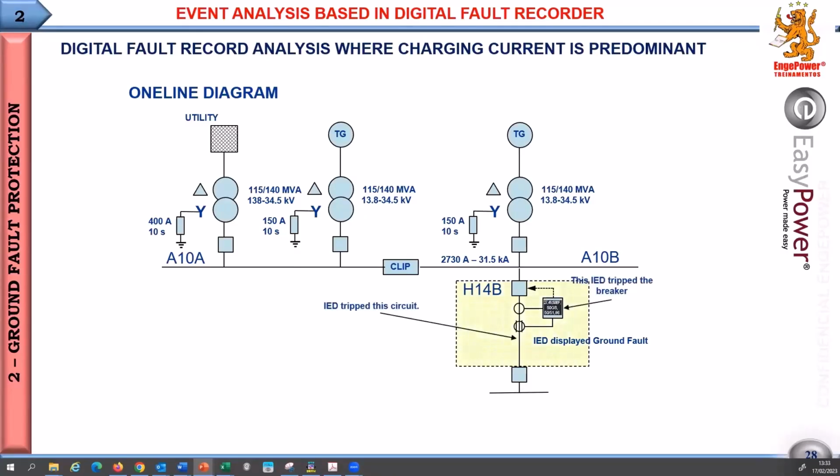One day, this IED tripped, indicating ground fault. Ground fault. So it tripped this breaker here and opened the circuit. Everyone thought that it was a ground fault on this circuit.